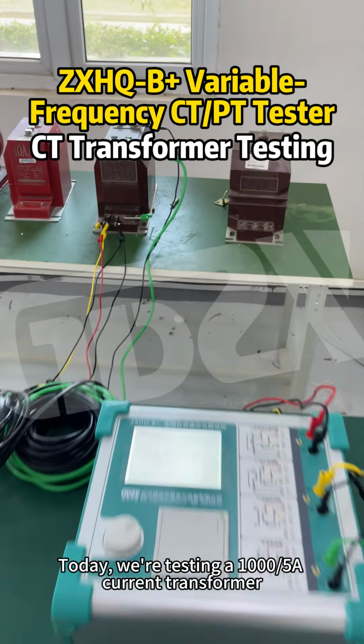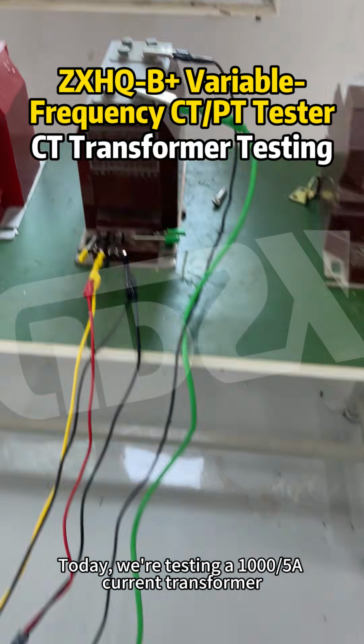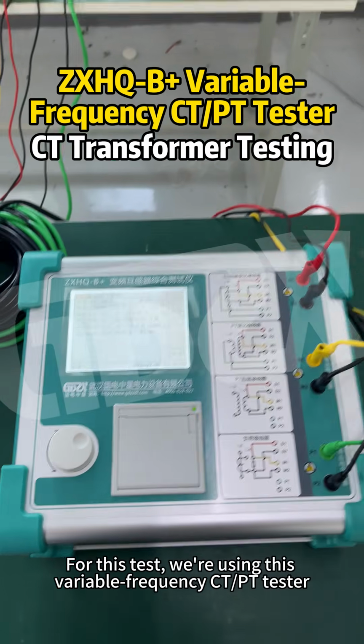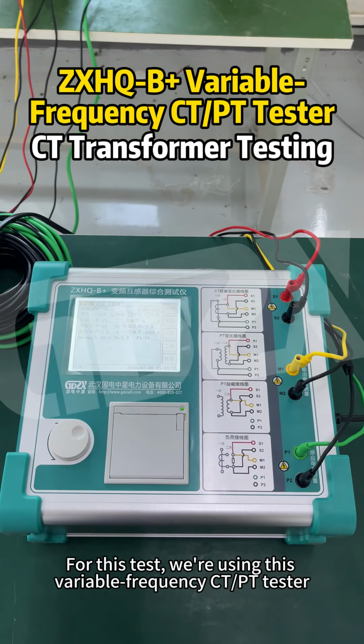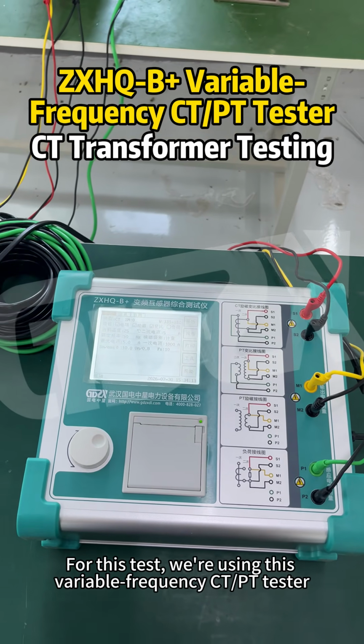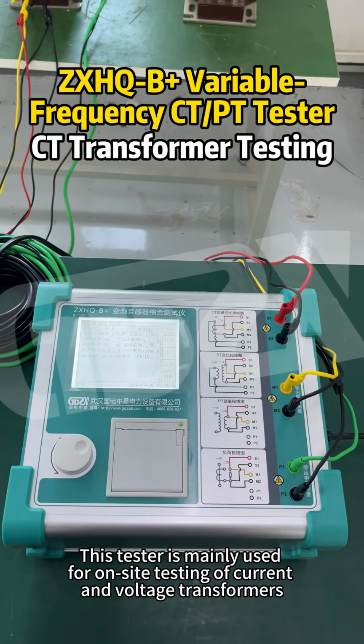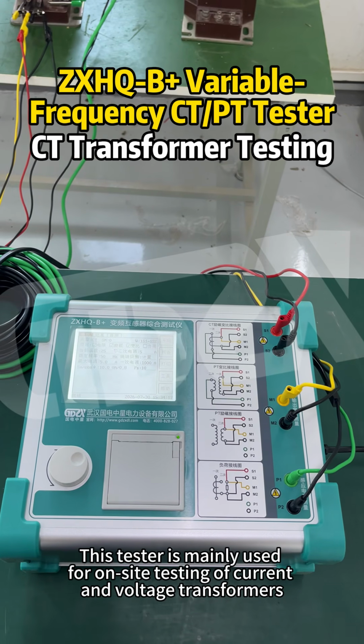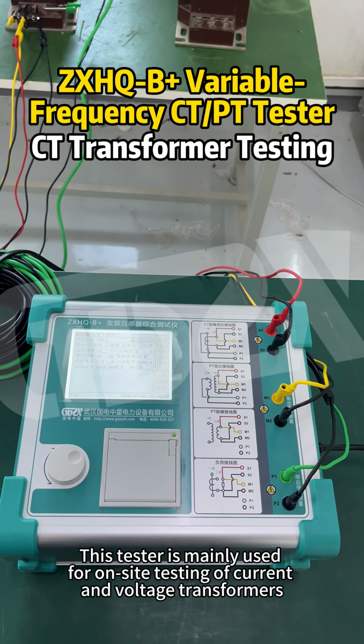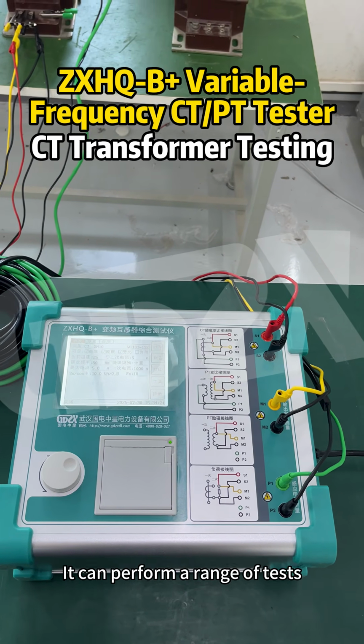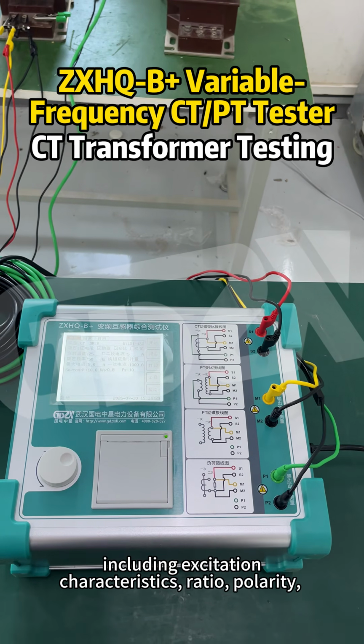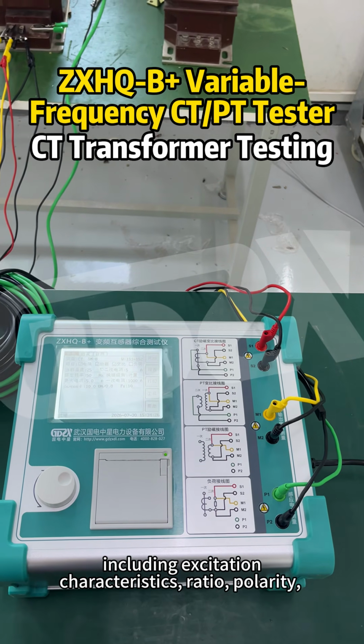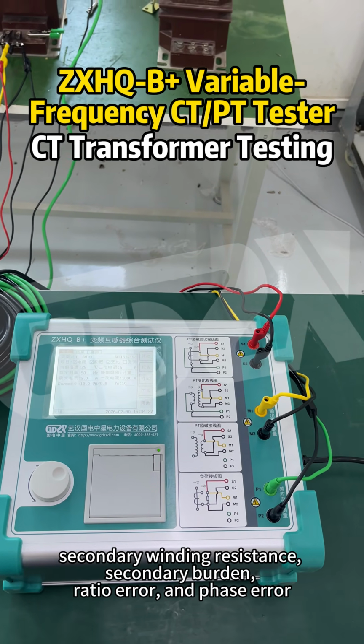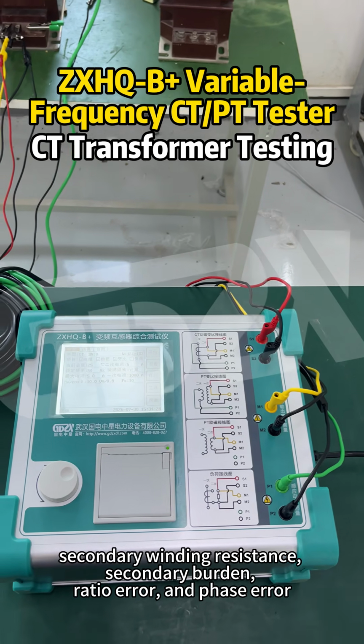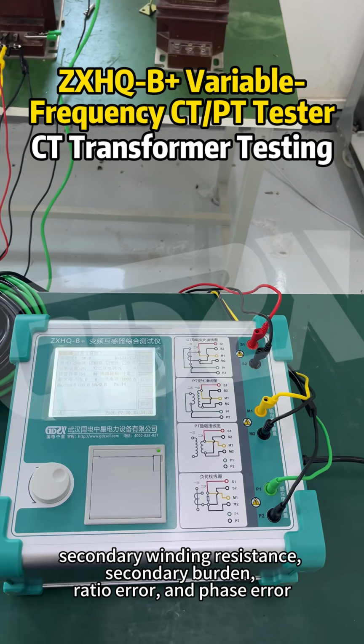Today, we're testing a 1000/5A current transformer. For this test, we are using this variable frequency CTPT tester. This tester is mainly used for on-site testing of current and voltage transformers. It can perform a range of tests, including excitation characteristics, ratio, polarity, secondary winding resistance, secondary burden, ratio error, and phase error.